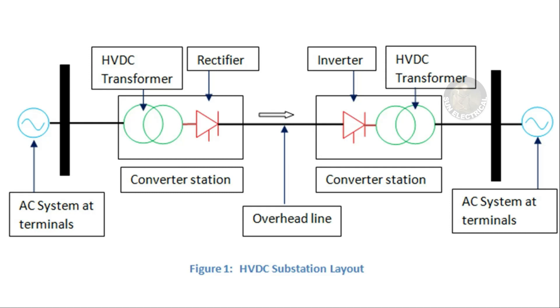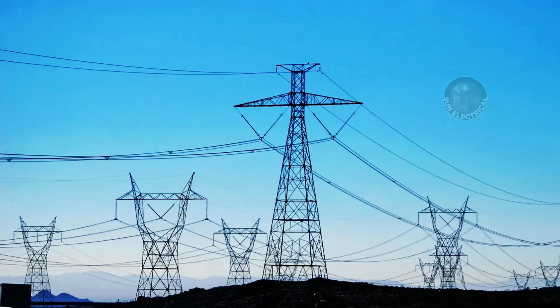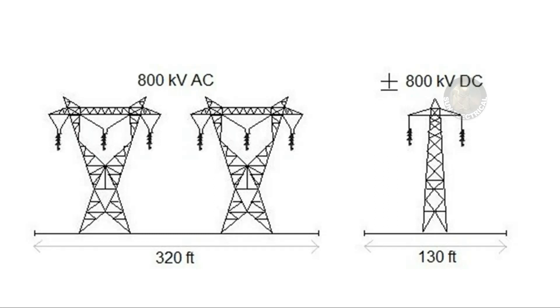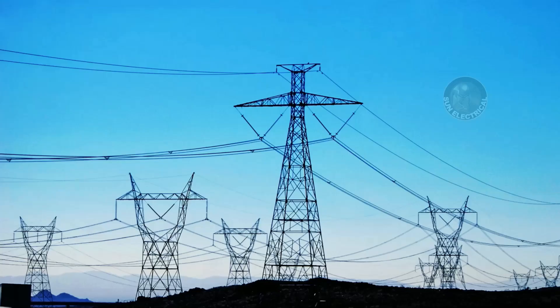The HVDC line has more power transmission capacity, and the tower size is smaller. It will allow much more power transmission. If you compare HVAC to HVDC cost, you don't have to use as many insulators. So for long transmission, HVDC cost is a big advantage over HVAC.